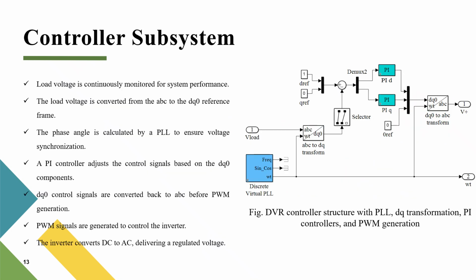Controller subsystem. This subsystem performs voltage regulation. The measured load voltage is converted into the DQ0 frame using a phase lock loop. The D and Q components are compared with their respective references. Errors are passed through PI controllers and the outputs are transformed back into ABC signals. These are used to generate PWM signals for controlling the inverter.